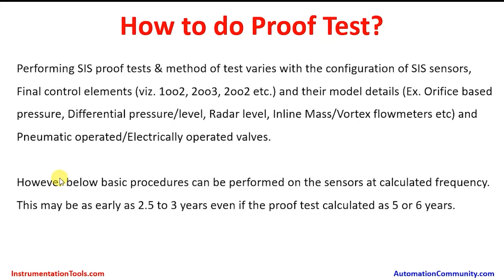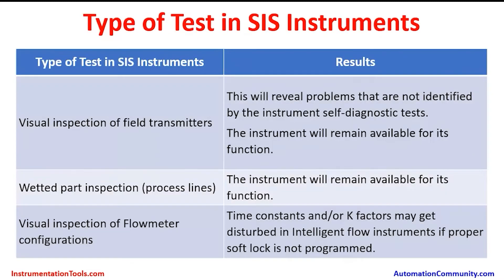The basic procedures below can be performed on the sensors at the calculated frequency. This may be as early as 2 or 3 years, even if the proof test is calculated for 5 to 6 years, as sometimes it may be required to perform at an earlier interval — perhaps due to a planned trip well before the planned target date or planned shutdown dates. The following types of tests are to be performed on the safety instrumented system instruments.